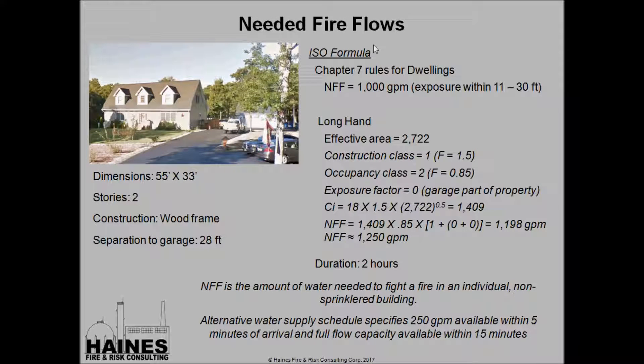The ISO needed fire flow formula has been around for quite a while. For dwellings, it has a simplified table where you look at your dwelling, measure the distance between your buildings, and pick your flow rate. In this case we come up with 1,000 GPM because we have an exposure within 11 to 30 feet of our building. You can also do it longhand, which requires calculating the effective area, construction class, occupancy class, exposure factor, and communication factor — arriving at about 1,250 GPM. The longhand doesn't get much different than the shortcut method.